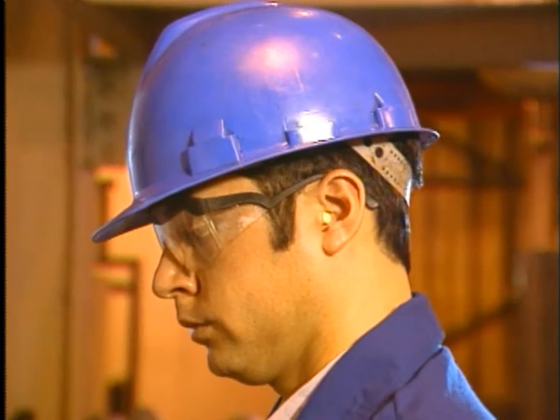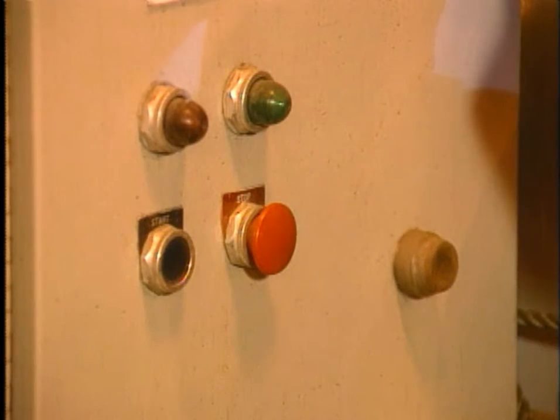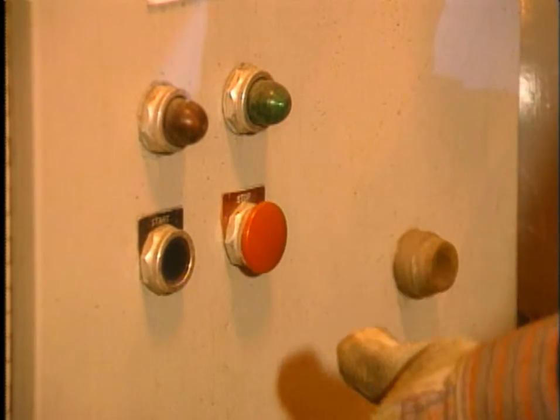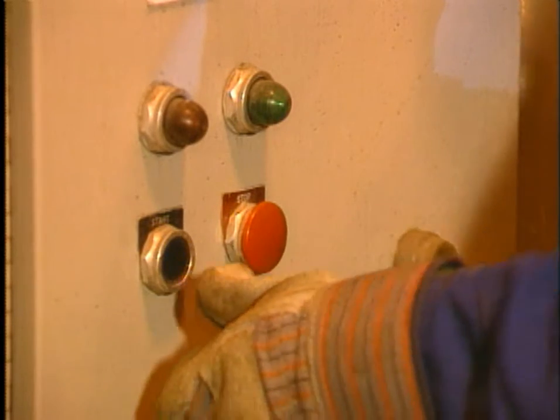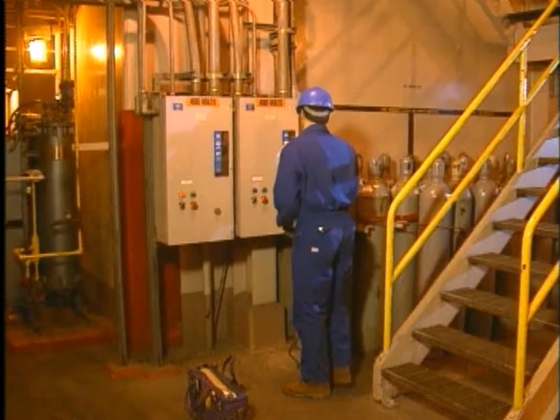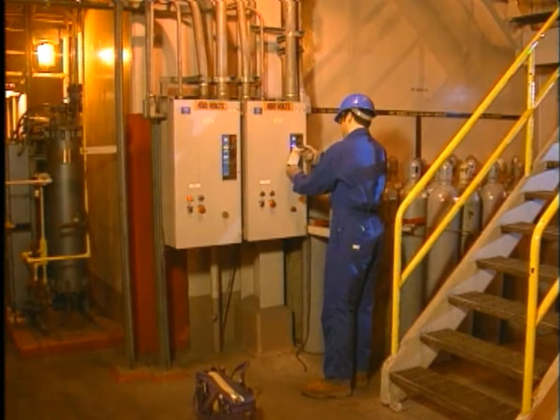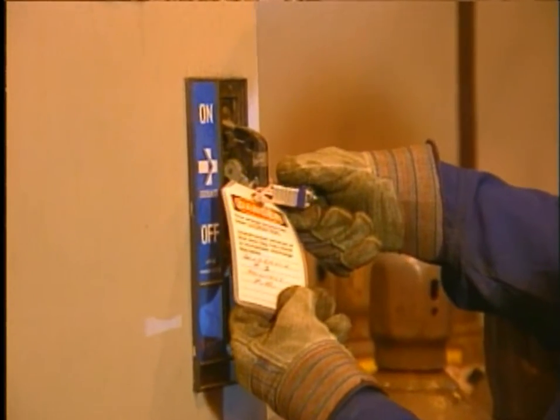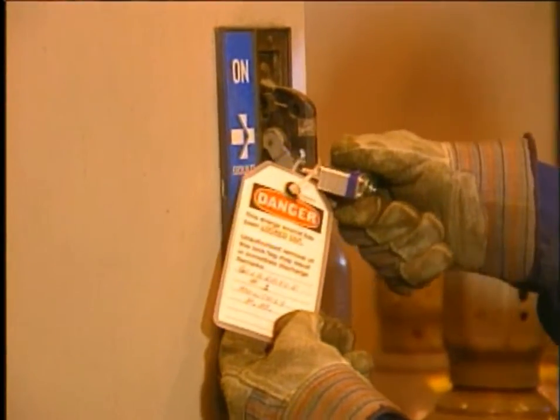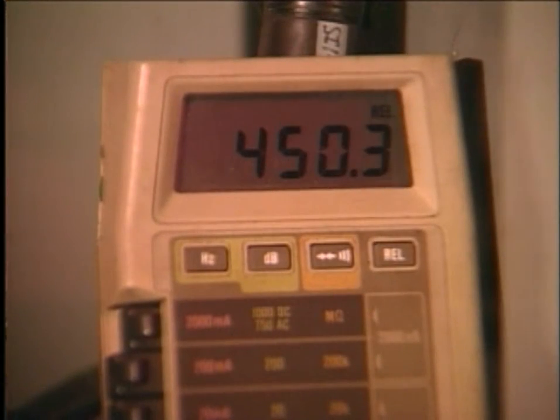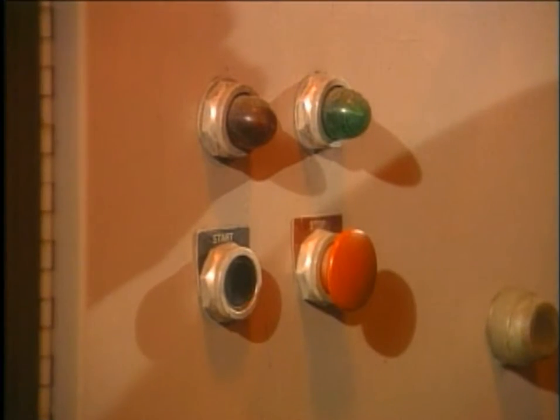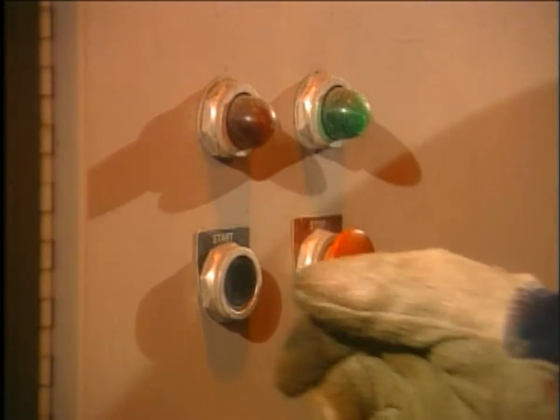After you're sure that no people are exposed, operate the energizing switch or other normal operating controls to make certain the equipment will not operate. Next, verify the main disconnect or circuit breaker cannot be moved to the on position. A voltmeter is used to check for voltage. Press all start buttons and other activating controls. Shut off all machine controls.